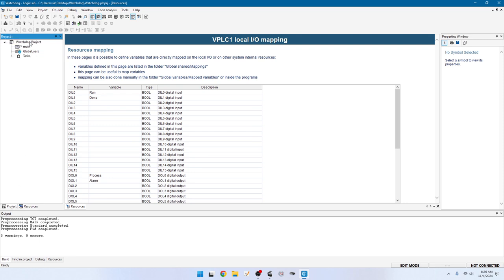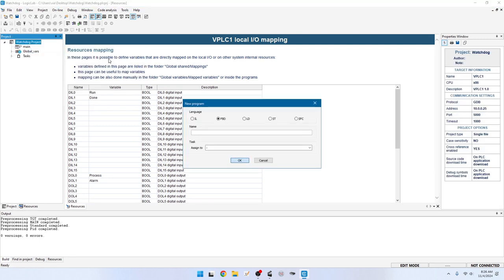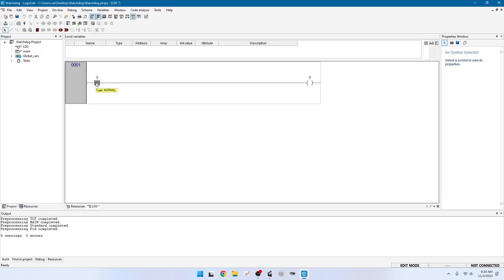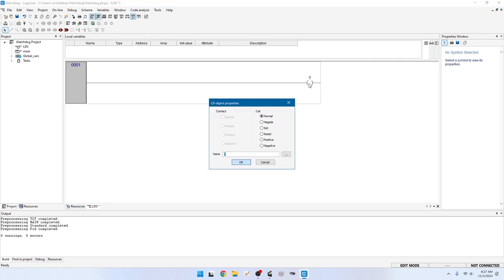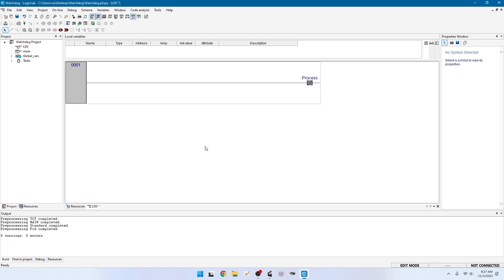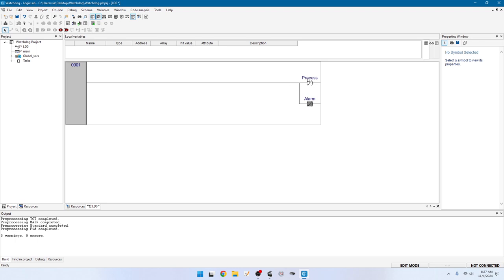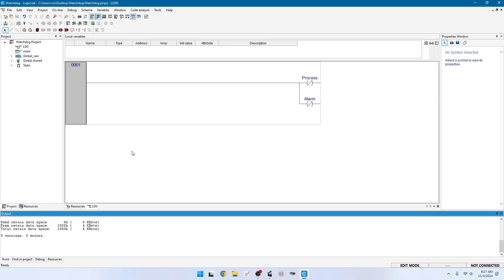Go back to Project and add a new program — ladder diagram, LD0, assigned to initialization. We're going to give initial values to variables. Delete the contact. Over here, set Process to negated — false or zero. We'd also like the alarm to be turned off, so right-click and put a new coil next to it — also a negated coil — with Alarm as the label. This sets both process and alarm variables to zero. Save, F7 — compiles fine.